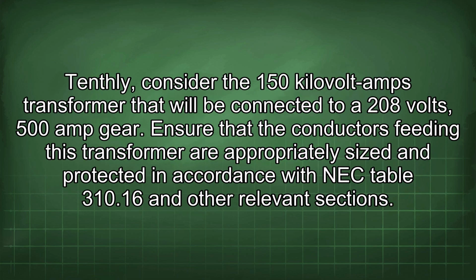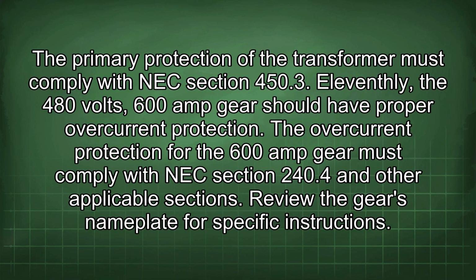Tenthly, consider the 150 kVA transformer that will be connected to a 208 volts, 500 amp gear. Ensure that the conductors feeding this transformer are appropriately sized and protected in accordance with NEC Table 310.16 and other relevant sections. The primary protection of the transformer must comply with NEC Section 450.3.